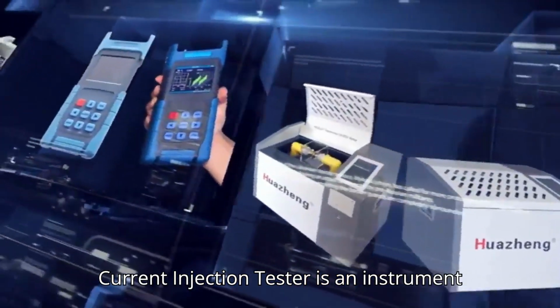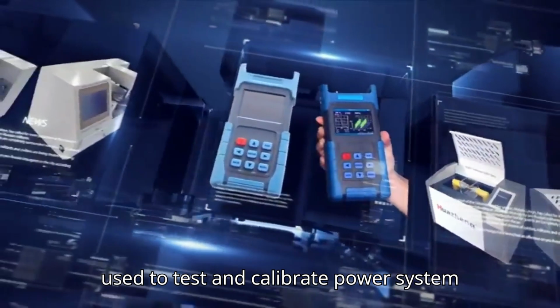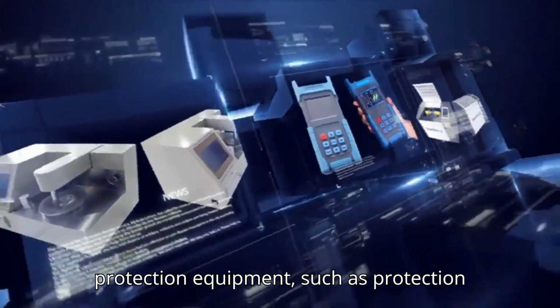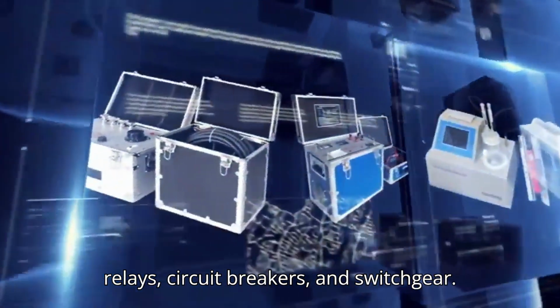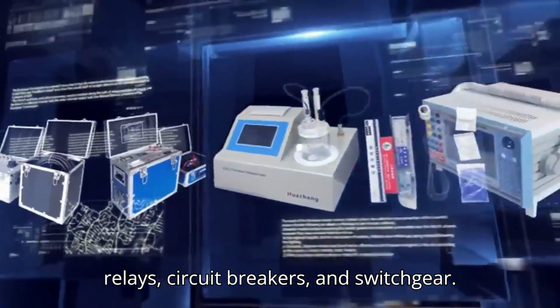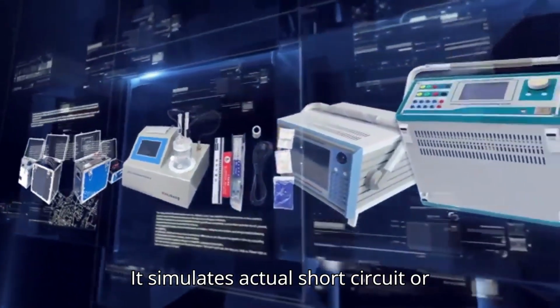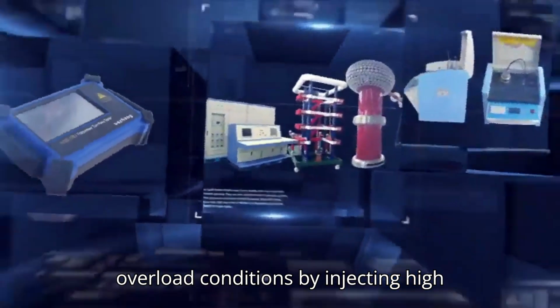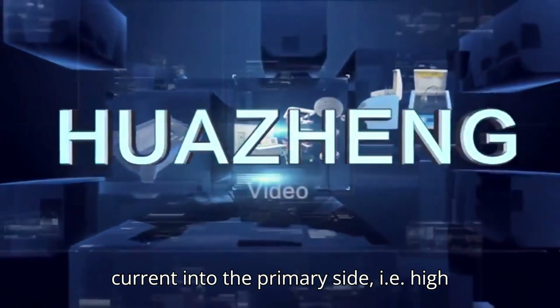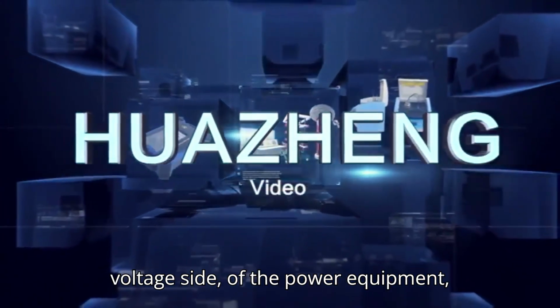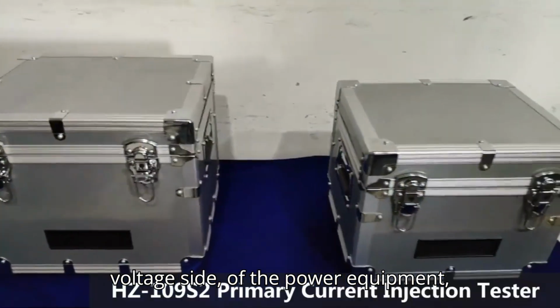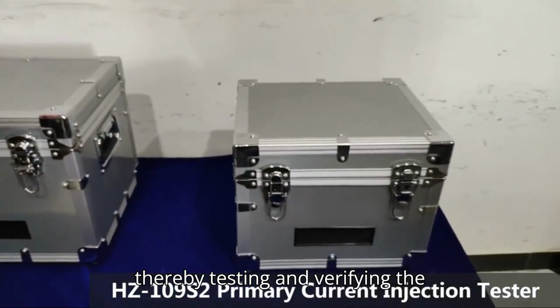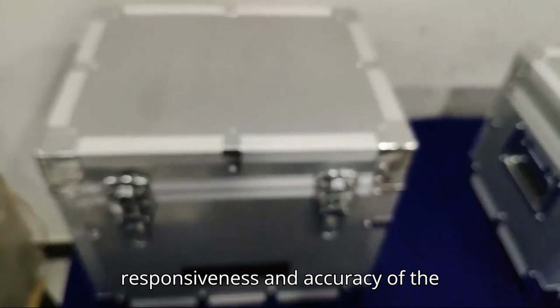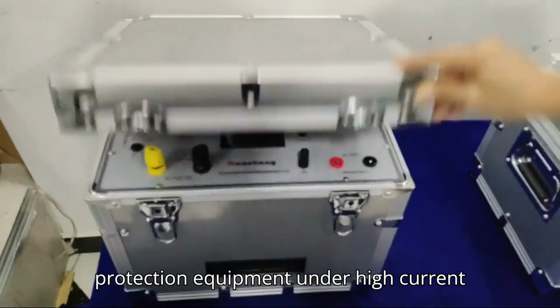The HZ-109S2 primary current injection tester is an instrument used to test and calibrate power system protection equipment, such as protection relays, circuit breakers, and switchgear. It simulates actual short circuit or overload conditions by injecting high current into the primary side, i.e., high voltage side, of the power equipment, thereby testing and verifying the responsiveness and accuracy of the protection equipment under high current conditions.